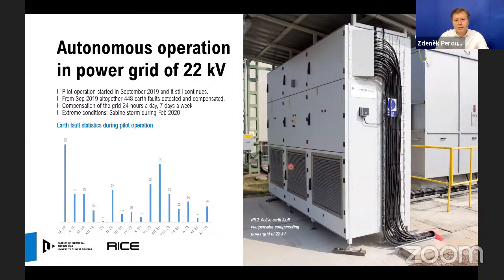In September 2019, we started the autonomous operation of our device in the 22 kV power grid. So we have already passed almost 2 years of pilot operation of this device in real grid operation. We faced around 500 earth fault strikes, which were detected and successfully compensated. We also had the chance to test our device under extreme conditions when we faced the Sabine storm in February 2020 in the Czech Republic.